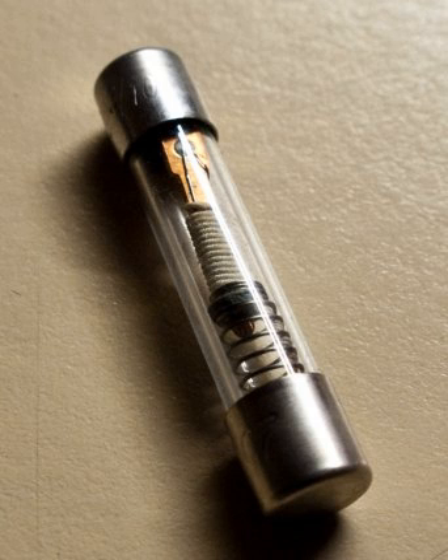Topic: Voltage drop. The manufacturer may specify the voltage drop across the fuse at rated current. There is a direct relationship between a fuse's cold resistance and its voltage drop value. Once current is applied, resistance and voltage drop of a fuse will constantly grow with the rise of its operating temperature until the fuse finally reaches thermal equilibrium.